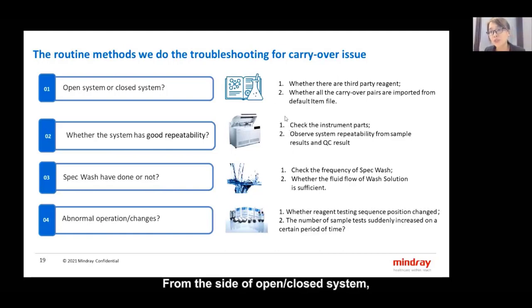From the side of open or closed system, we are going to confirm whether there are third-party reagents and whether all the carryover pairs are imported from the default item file. From the side of system repeatability, we will check the instrument parts and observe sample results and QC results. From the side of special wash, we are going to check the frequency of special wash and whether the fluid flow of washing solution is sufficient. For others, such as whether the reagent testing sequence changed, testing volume changed, or etc., we try to find the real reason as much as we can. You may have a question why we put the confirmation of whether the system is open or closed first, and I will answer it next.